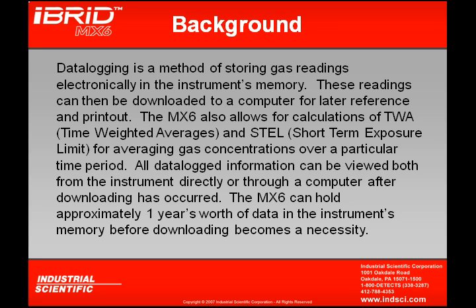The MX-6 also allows for calculation of TWA, which is time-weighted average, and STELs, which is short for short-term exposure limit, for averaging gas concentrations over a particular time period. All data logged information can be viewed from the instrument directly or through the computer after downloading. The MX-6 can hold approximately one year's worth of information in the instrument's memory before downloading becomes a necessity.